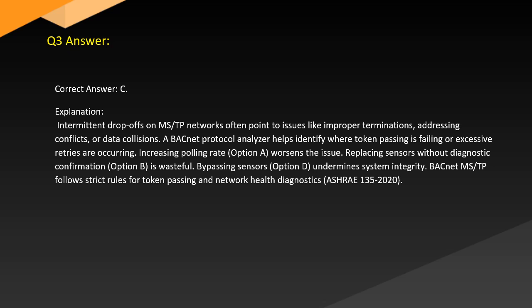Increasing polling rate, option A, worsens the issue. Replacing sensors without diagnostic confirmation, option B, is wasteful. Bypassing sensors, option D, undermines system integrity. BACnet MS/TP follows strict rules for token passing and network health diagnostics. ASHRAE 135-2020.